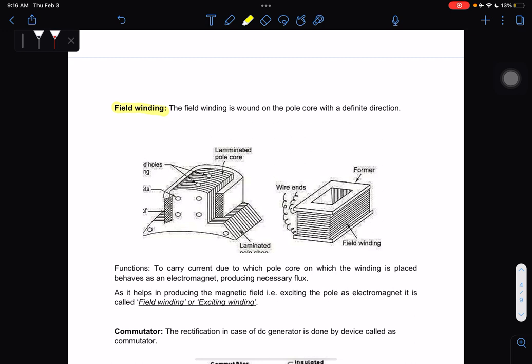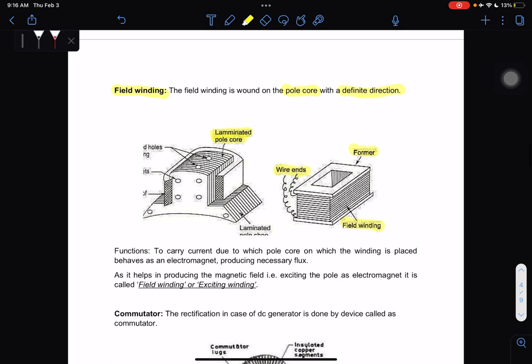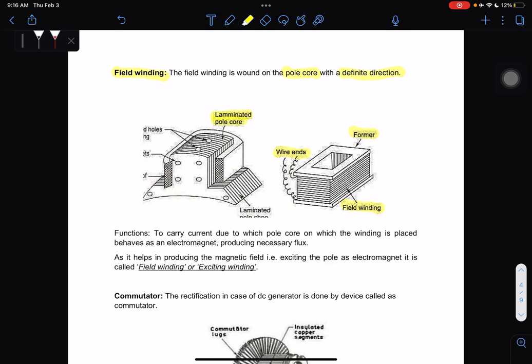We have the field winding. The field winding is wound on the pole core with a definite direction. Its function is to carry a current, due to which the pole core on which the winding is placed behaves as an electromagnet and produces flux. It helps in producing the magnetic field, and it is called field winding or exciting winding.